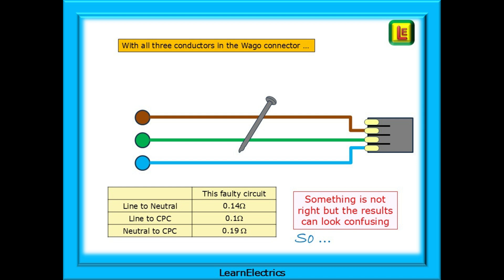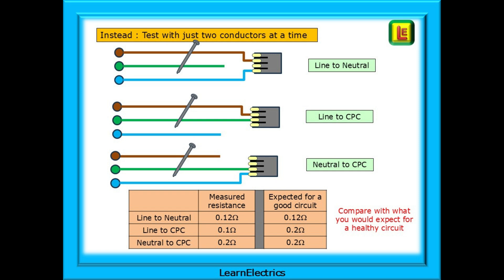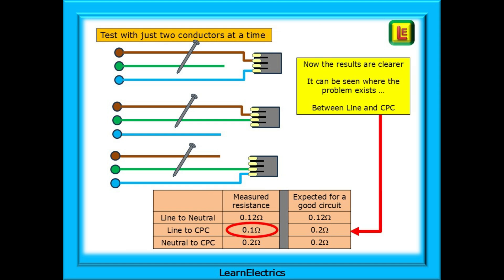Instead, test with just two conductors at a time. Just remove one conductor at a time from the Wago and retest on low ohms. Record your results and compare them to what a good fault-free circuit should measure. Now the results are clearer and it can be seen where the problem exists. With only two conductors connected together at any one time we find that the line to neutral and neutral to CPC show the same results as a healthy circuit, but line to CPC gives a completely different reading — and we can be fairly confident that the problem is between line and CPC. As the fault involves the earth or CPC, we call this an earth fault rather than a short circuit.